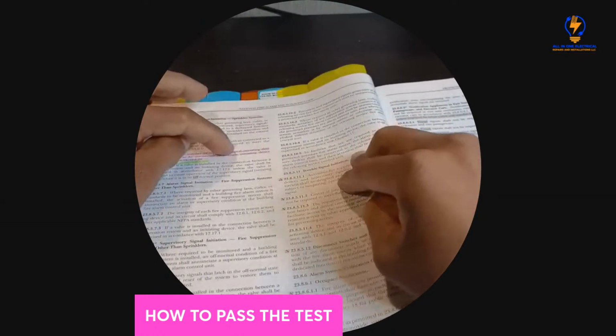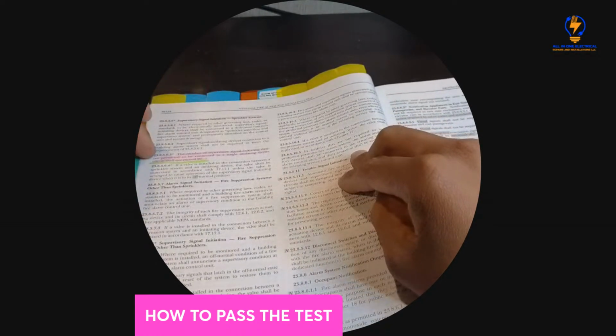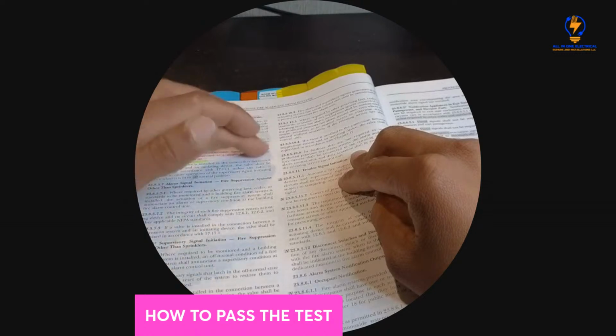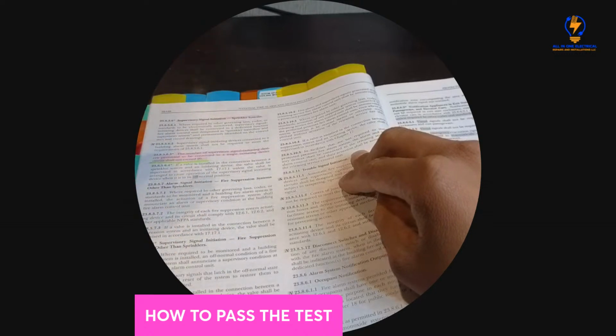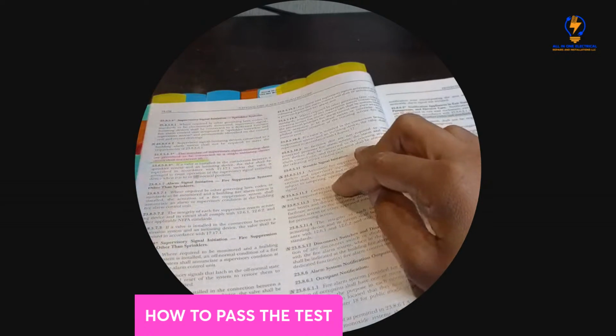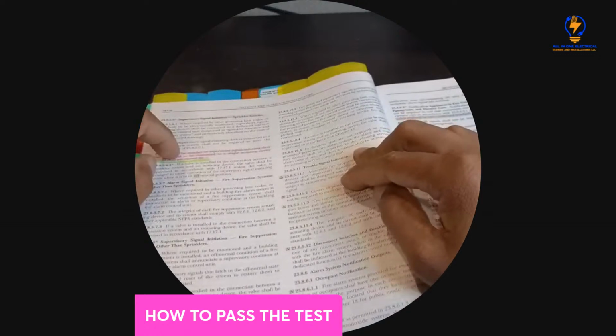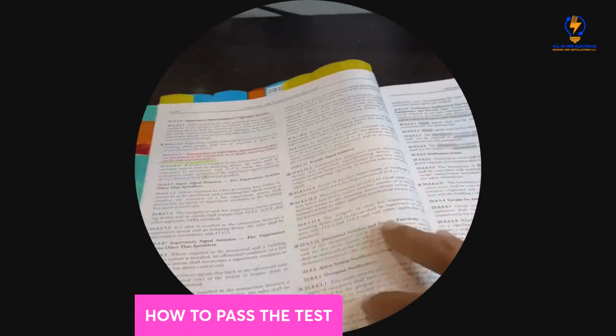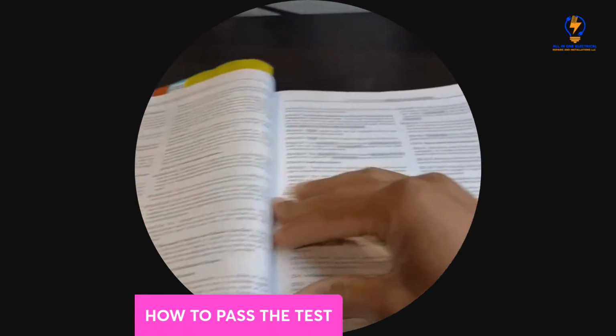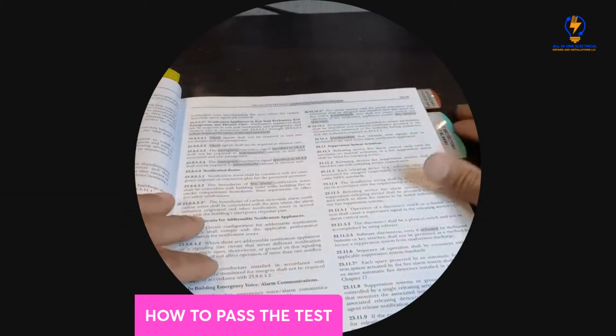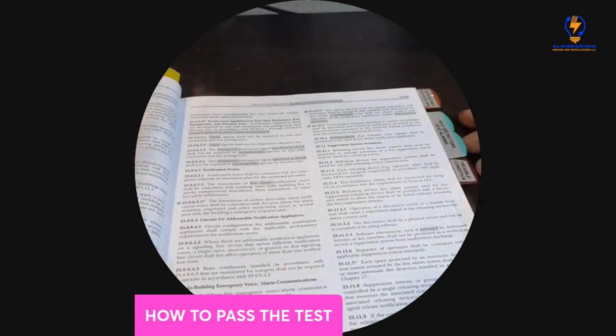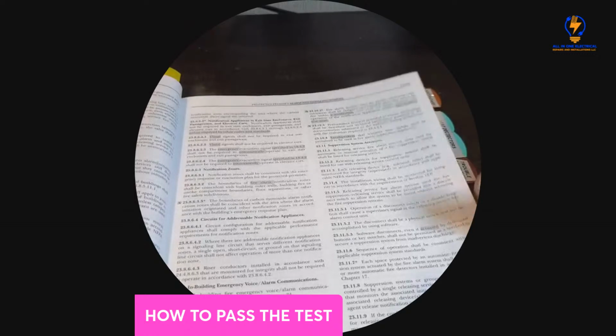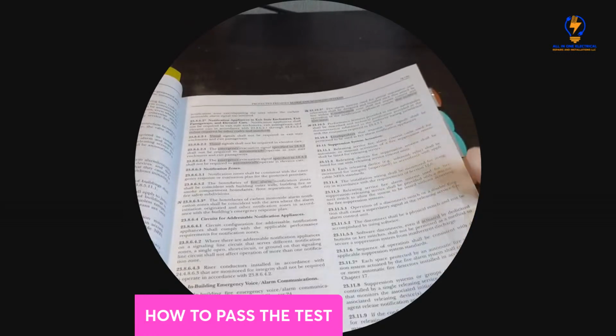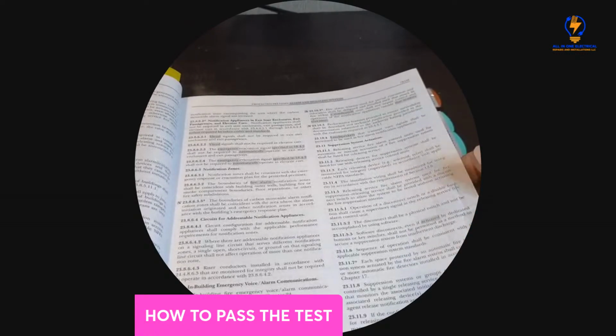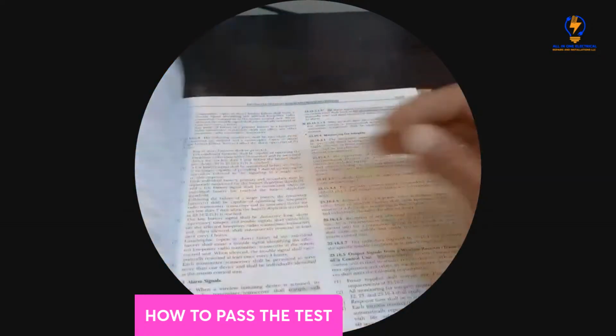The number of supervisory signal initiating devices permitted to be connected to a single initiating device circuit shall not exceed 20. Very, very important. Giving you gems that they won't miss those things in the test. As a tab, put supervisory signal initiating sprinkler or supervisory signal initiating devices. Tab to the side.